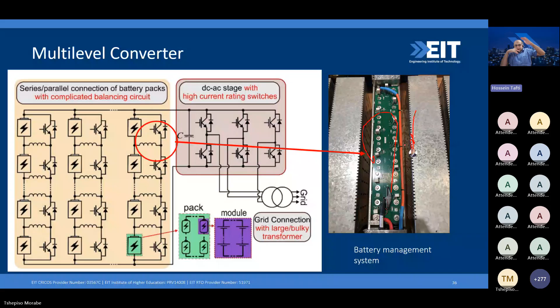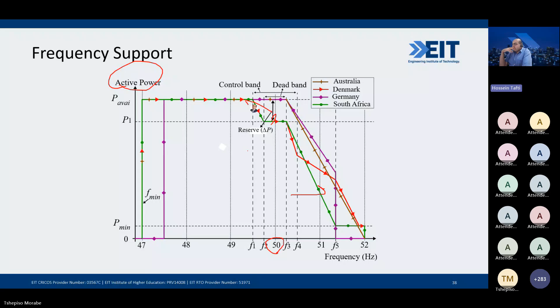Now we come to power system support, and there are a few functionalities a battery system can provide. One of them is frequency support. If the frequency of the system deviates from the nominal frequency, shown here as 50 Hertz, the battery system could decrease its output power, or it could increase its output power, as shown from this point on the power axis. The main point is to keep some amount of reserve power, so that under sudden changes or reductions of the grid frequency, the battery is capable of injecting higher power into the grid. That's what frequency support means.